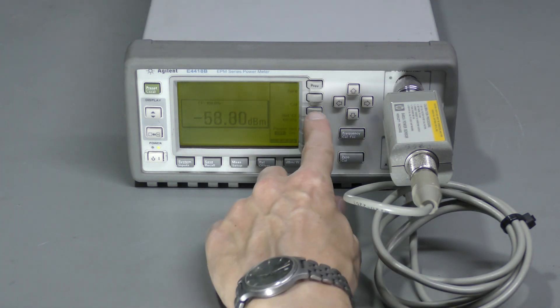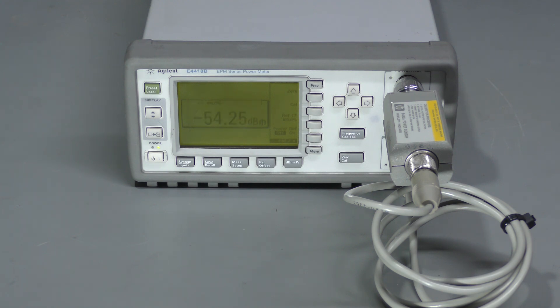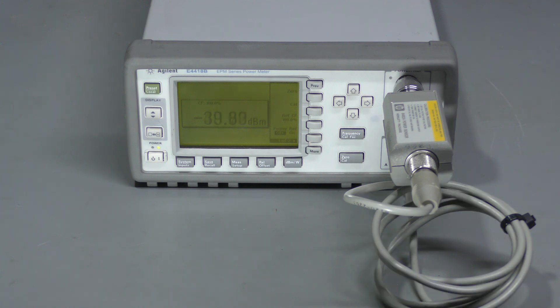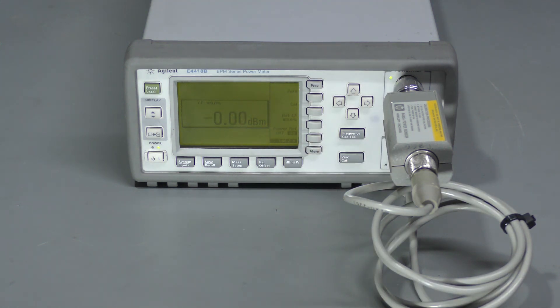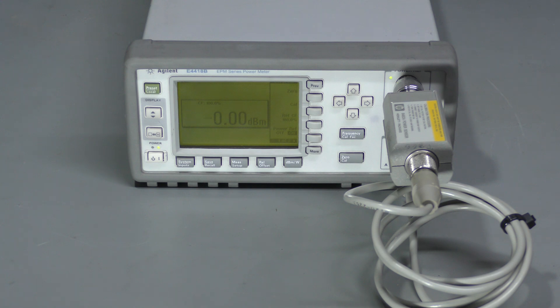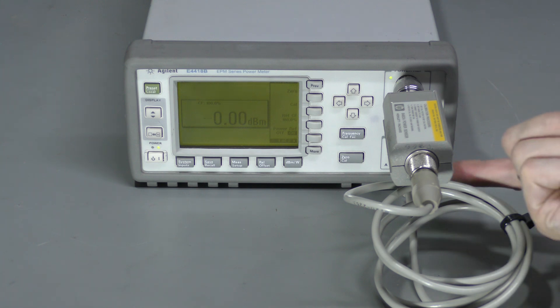Then cal. And now if we turn on the reference output. There you go. Exactly zero dBm. And for now I ignored the calibration constants marked on the sensor. For this simple test it should be good enough. I believe the instrument is working fine.